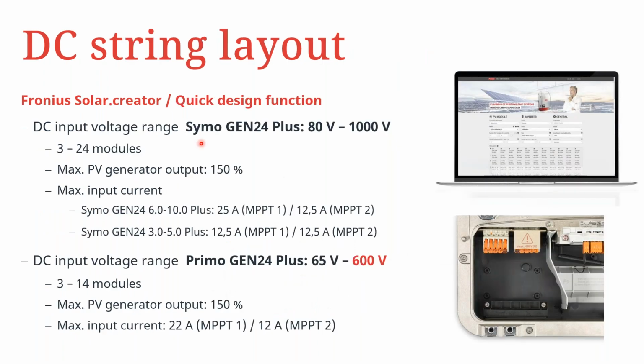If you want to be sure that you have designed the right kind of string connection for either the Symo GEN24 or the Primo GEN24, then you can make use of the Fronius design tools. So we have the Fronius Solar Creator, and within the Solar Creator, we have a quick design function that allows you to verify the string configuration that you want to use for any particular inverter.